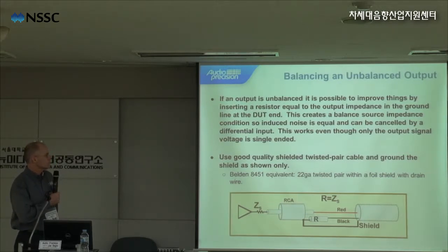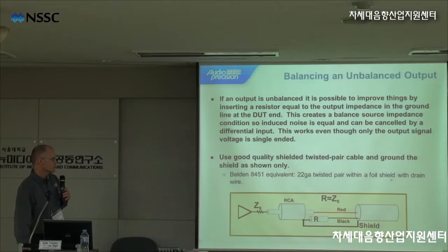Balancing an unbalanced output. If an output is unbalanced, it's possible to improve things by inserting a resistor equal to the output impedance in the ground line at the device under test end. This creates a balanced source impedance condition, so induced noise is equal and can be canceled by a differential input. This works even though only the output signal voltage is single-ended. So we have here a single-ended unbalanced connection, and we're inserting a resistance between the shield and ground to try and balance with the source impedance. Use good quality shielded twisted pair cable and ground the shield as shown here in the diagram. So Belden 8451 or equivalent, it's a 22 gauge twisted pair within a foil shield with a drain wire.